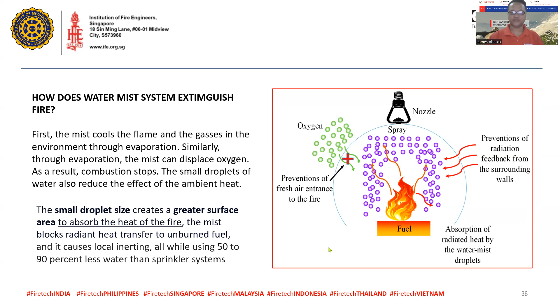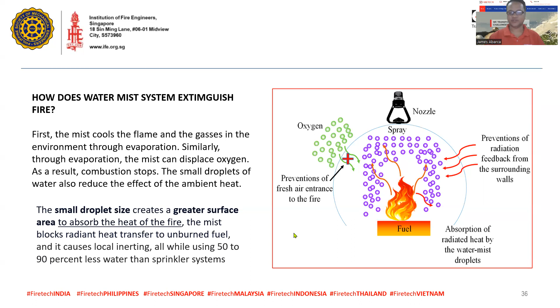Okay, so it removes heat and oxygen. The small droplet size creates a greater surface area to absorb the heat of the fire. The mist blocks radiant heat transfer to unburned fuel as well, and it causes local inerting, okay? And while using 50 to 90% less water than the sprinkler, I think that's one of the good news there. It is, if your client wants to save water or wants to use a smaller water tank, this system is a much more applicable alternative to the sprinkler system.